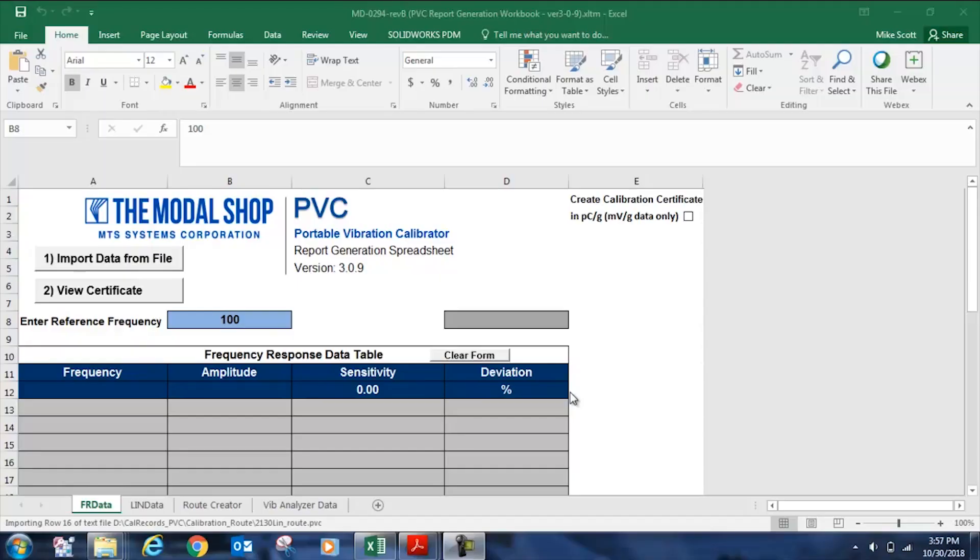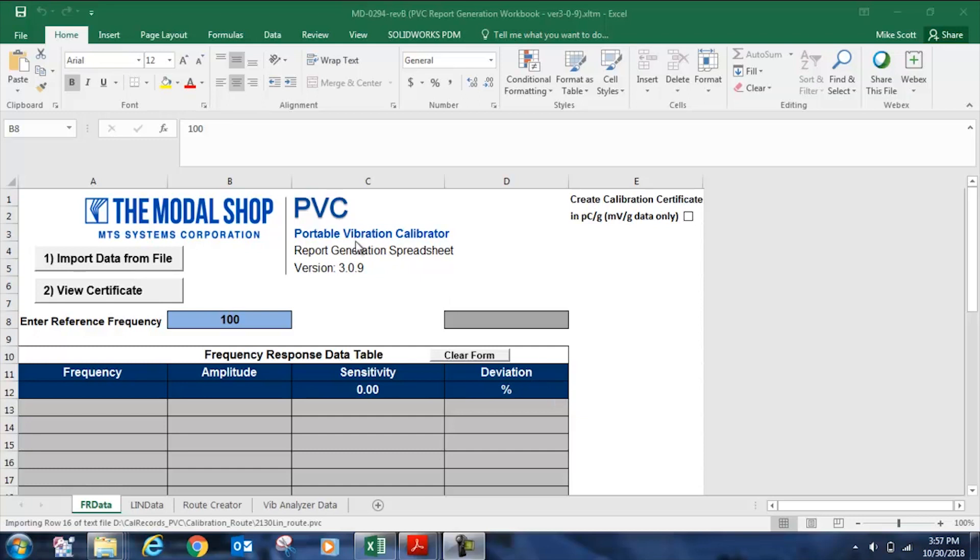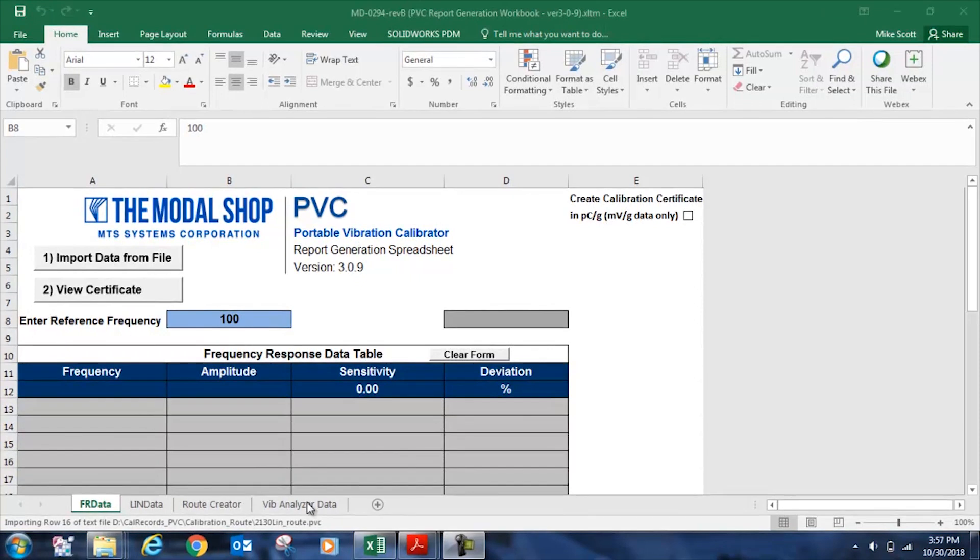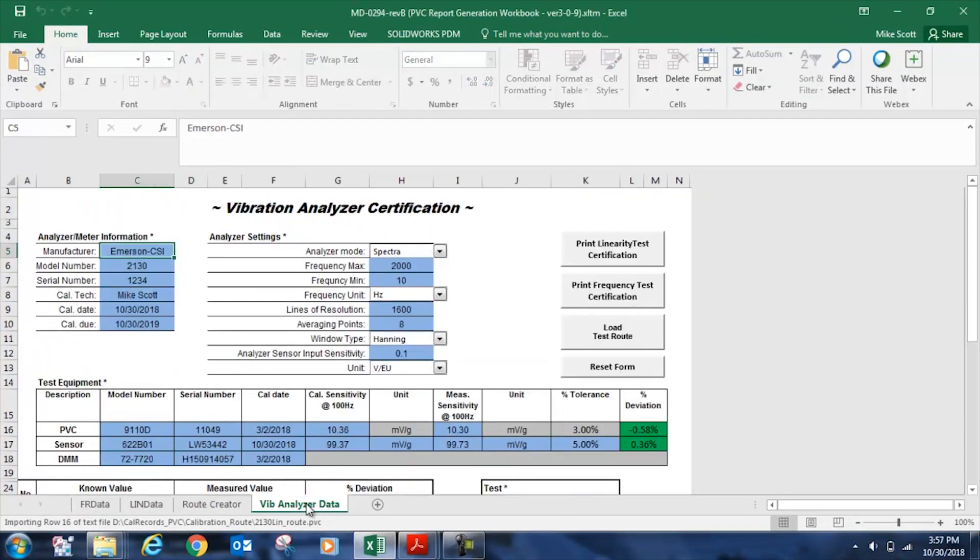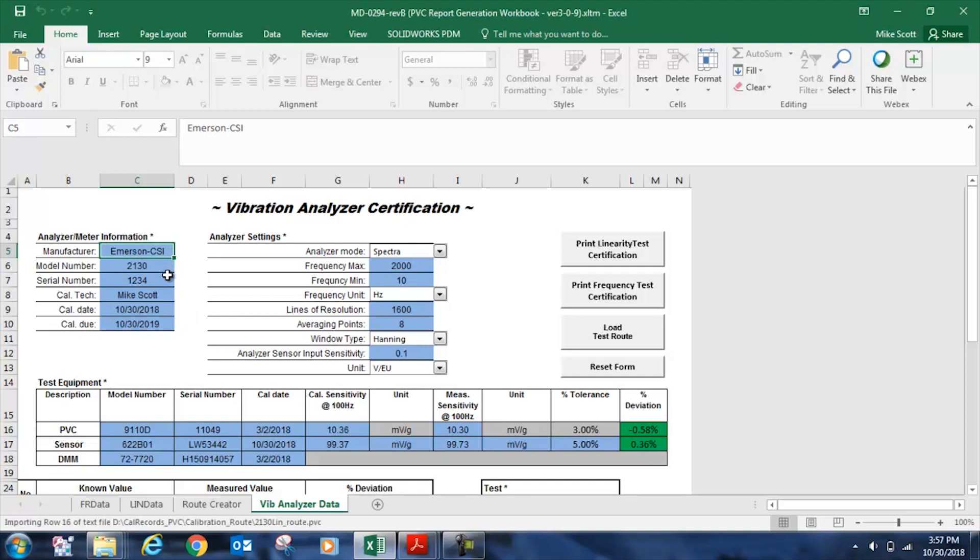Now that we have tested the accelerometer that we'll be using with the 2130 as well as our 9110 calibrator and documented our settings or reviewed our settings, we need to document that information. This is the report generation workbook supplied with the 9110D, and we click on vibration analyzer data to enter the information that we just accumulated. You can see that I've already entered in my Emerson CSI information here, as well as the date of calibration, and one year later when the next calibration is due. And I've noted the model number of 2130.